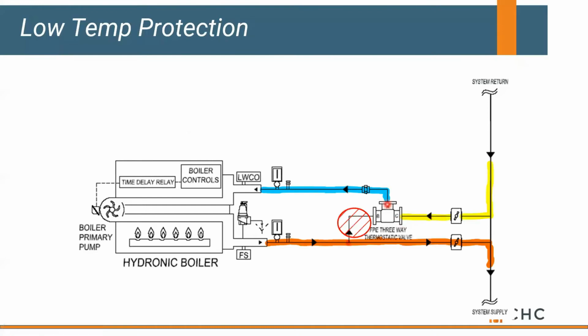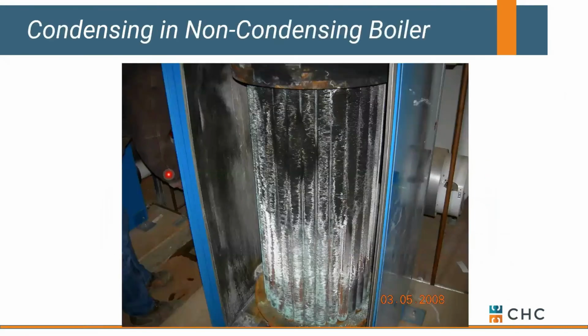Once we get our return above 130, we start to send hot water out to the system. And once all our system heats up and gets above 130, then we close the bypass altogether. Okay, but there's going to be times when this modulates and allows a little bit of system water in and continues to bypass some hot water. But these are all low temp protection if you decide to go with a non-condensing boiler. I hope that all that makes sense.